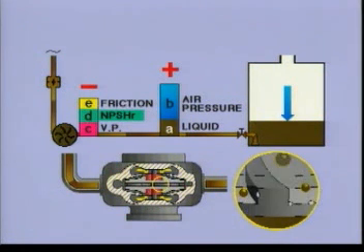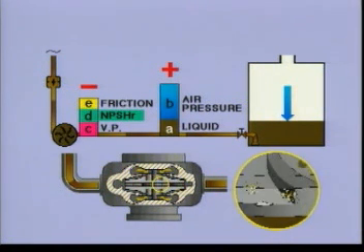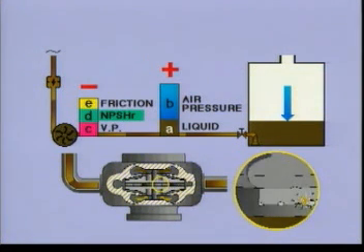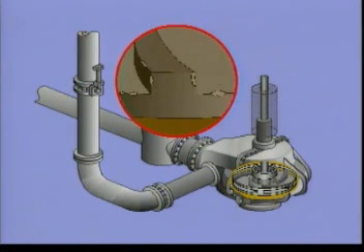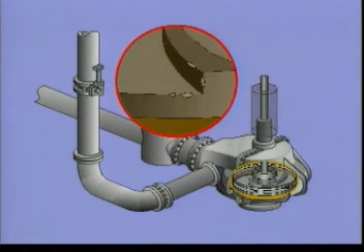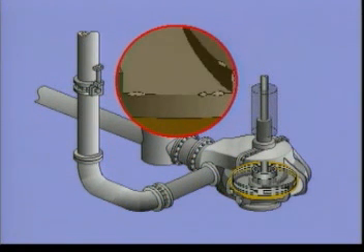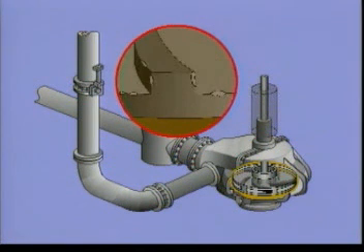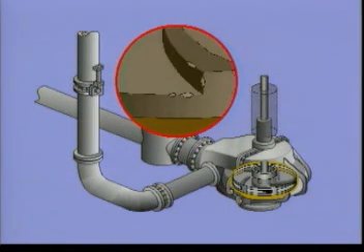Small bubbles grow, and when they meet the higher pressure in the periphery of the pump, they collapse. This is cavitation, and must be avoided, as the capacity of the pump will be reduced, and it can easily be permanently damaged. You can easily hear when a pump cavitates. It sounds like you're pumping gravel.